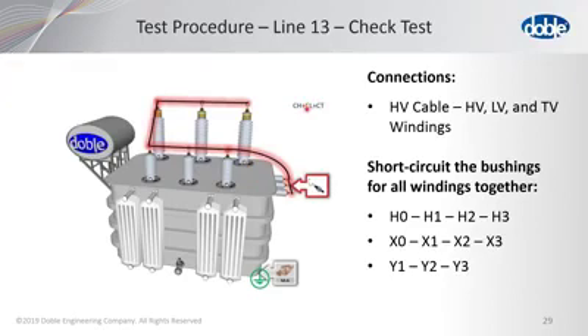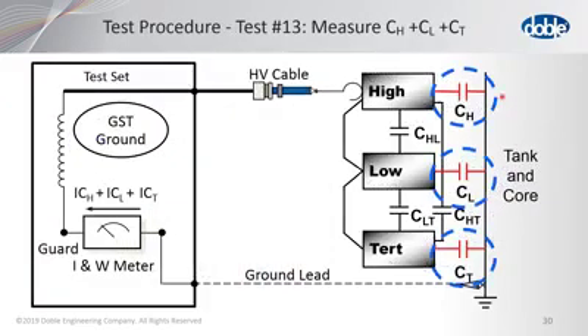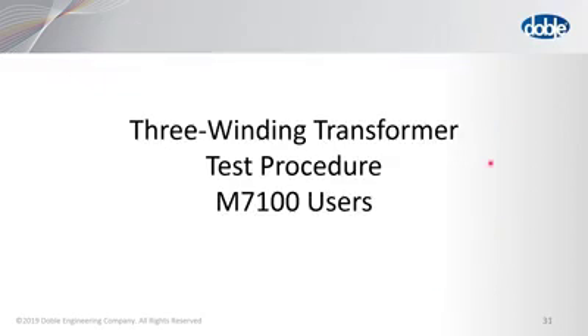Notice you do not need any low voltage leads for this test. All the current is going to be coming back through the ground lead. Remember to drop the low voltage lead to the ground and then disconnect them from the test set. Here is the test right here. You're measuring CH, CL, and CT in parallel, so you're measuring all those insulations.